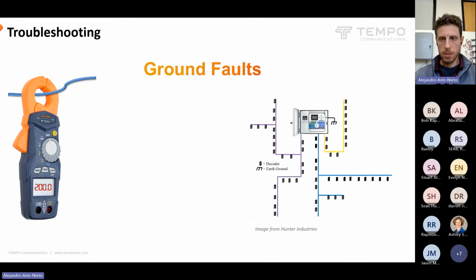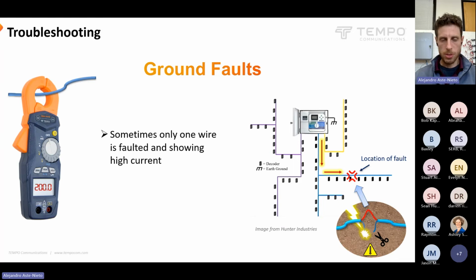A ground fault, again, sometimes it's only one wire that's faulted and giving you high current. So that current is leaking out through the dirt, and the other wire might be giving you normal numbers. So for that reason, you'll always want to check both wires. You might see a normal number on red, not realizing that blue might have its own issue.